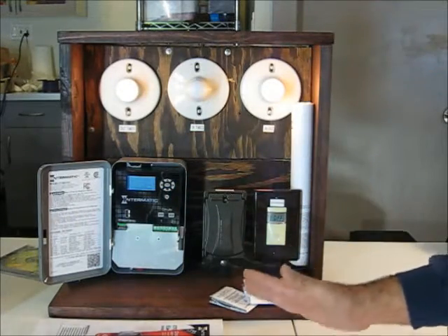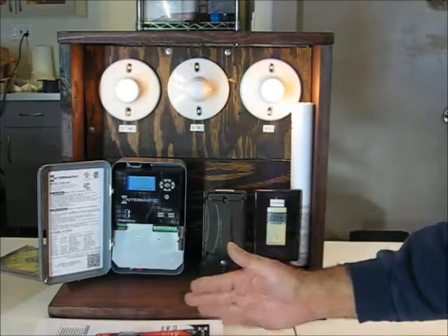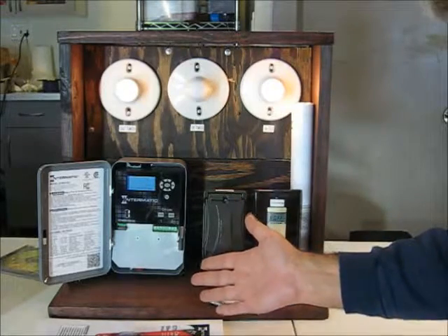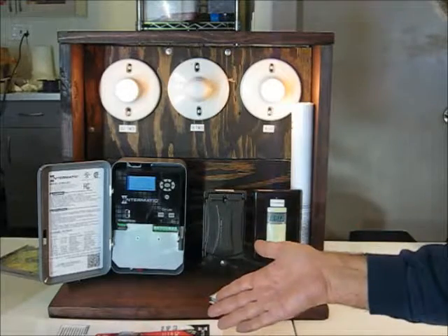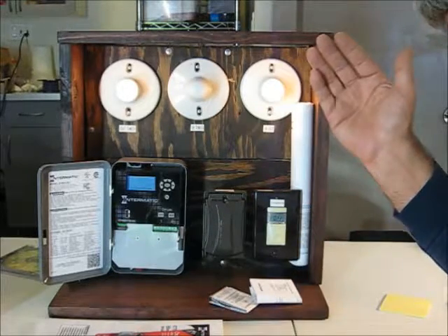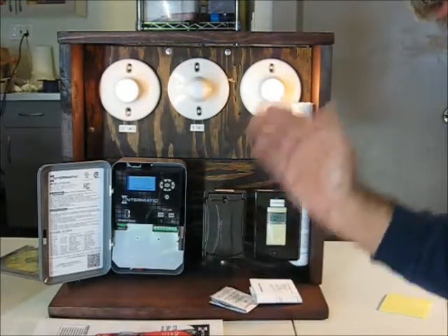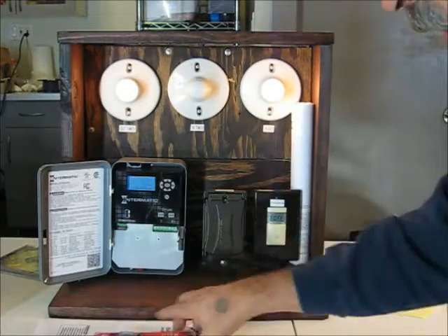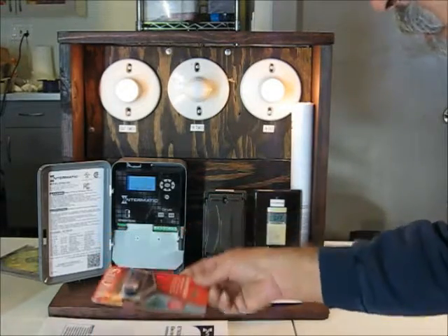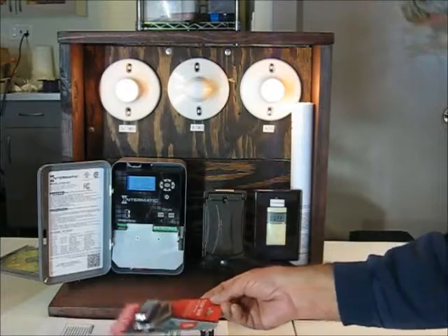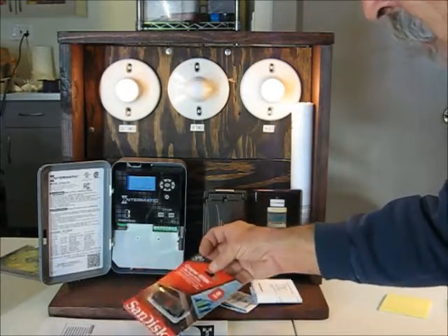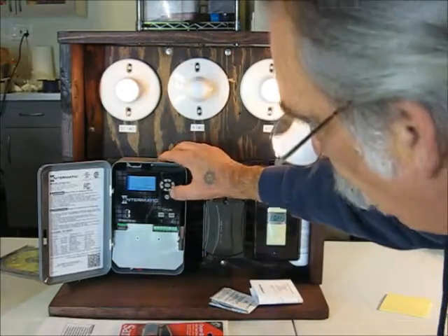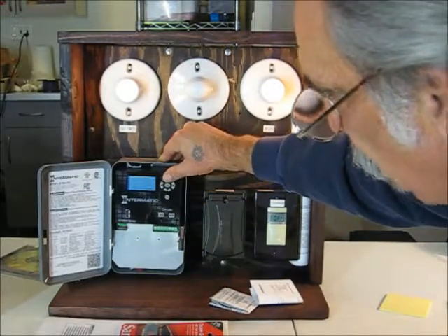Now if you do that, it's going to clear the program, but the timer will function okay once you get it set up. Then you go into initial setup, give it the date and time, and tell it no, I don't have any events and whatnot, and then you put in your program. Actually, you would load the program first, sorry, and then go to initial setup or just set the current date and time.